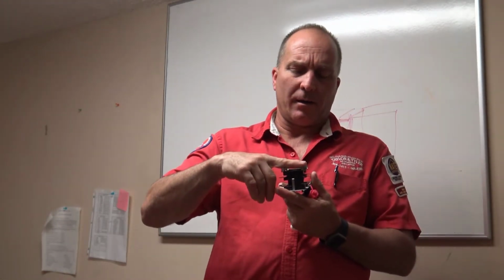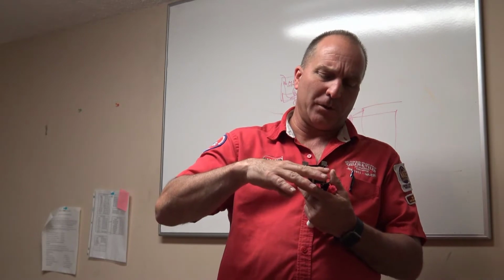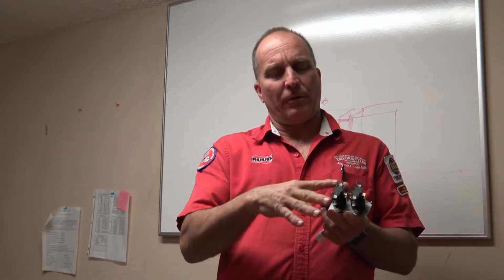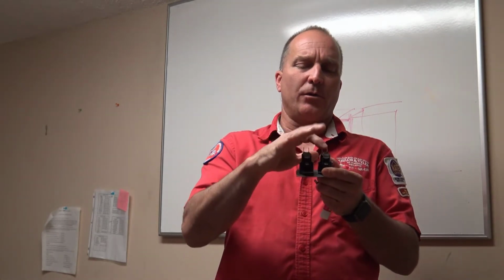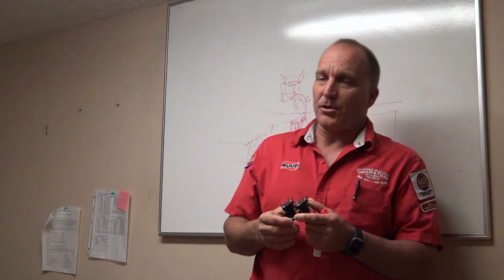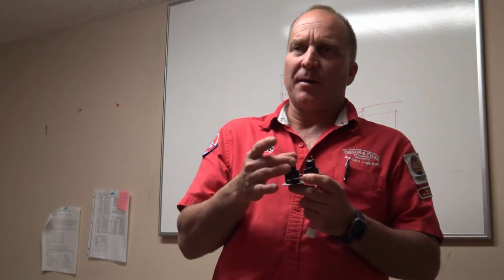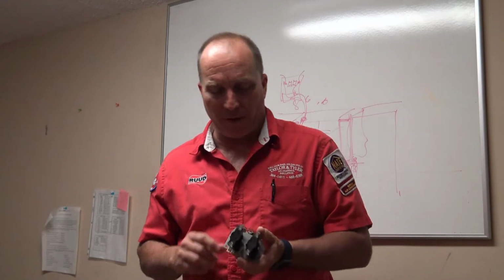That will then energize and close your normally open switches here, normally open switches here. Because you have a total of 8 openings on here, 4 total openings on here, normally open switches, when you energize them, they are going to energize up 1, 2, 3, 4, okay? And then they will close back on 1, 2, 3, 4 as well. So as it opens one way, it'll close back the other way, all right? The reason they do that is so that you don't have each 5 kW heat strip turn on at the same time and cause a power surge. That's the reason you do that, okay?